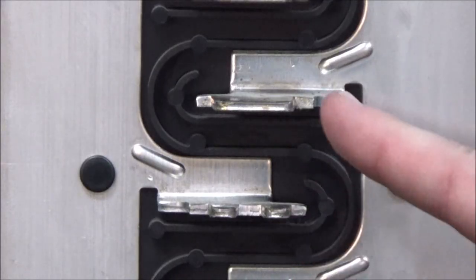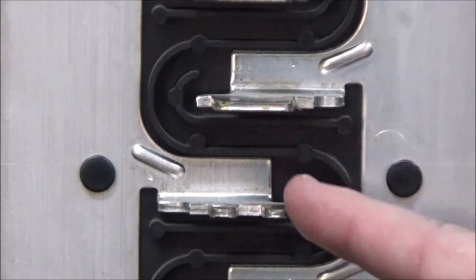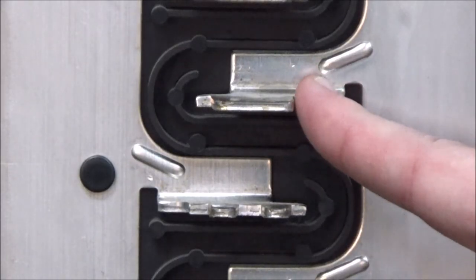However you'll see that the space above it has a fully flat bus bar. If the space has a fully flat bus bar like that it will not accept a tandem breaker.